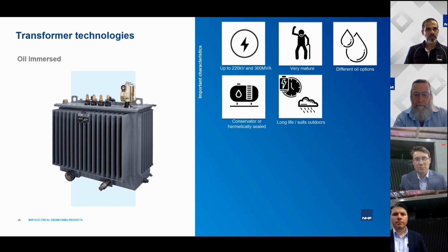And of course, it's important to detect any developing faults like internal arcing faults early on, so it doesn't lead to catastrophic failure of the transformer, which, as we're going to see in a few slides, may even result in a fire. But the purpose of this device is to prevent those faults early on and trip the HV circuit breaker.